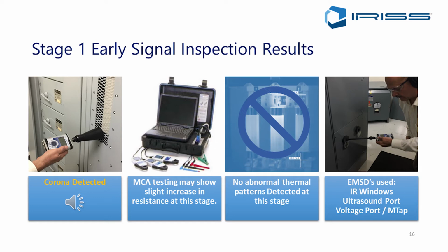Now, if you've got a phase imbalance, that's a different story. If you've got a 30% imbalance on one phase versus the other two, yeah, absolutely, there's going to be a different level of heat seen on that one phase. So you kind of have to look at the load characteristics concurrent with infrared as well.